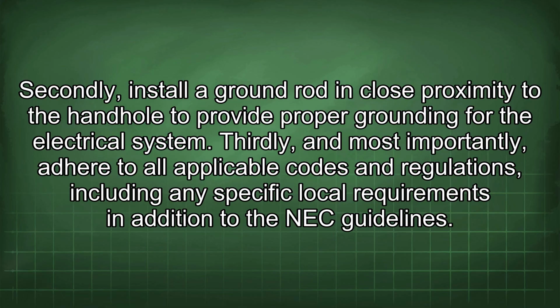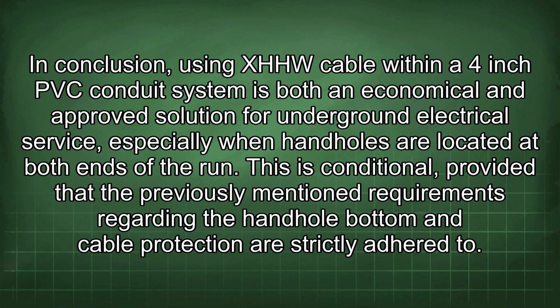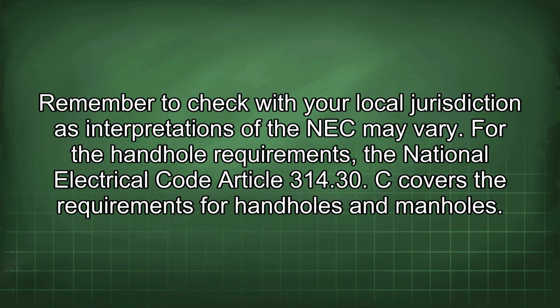In conclusion, using XHHW cable within a 4-inch PVC conduit system is both an economical and approved solution for underground electrical service, especially when handholes are located at both ends of the run. This is conditional, provided that the previously mentioned requirements regarding the handhole bottom and cable protection are strictly adhered to. Remember to check with your local jurisdiction as interpretations of the NEC may vary.